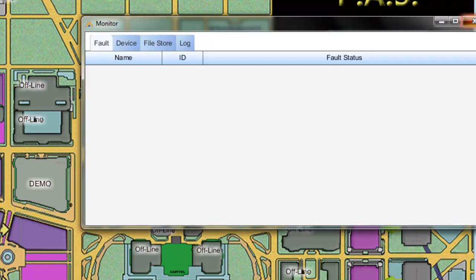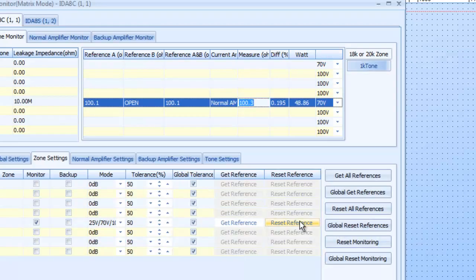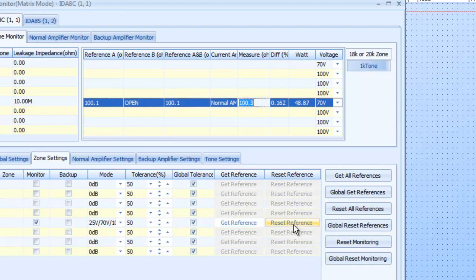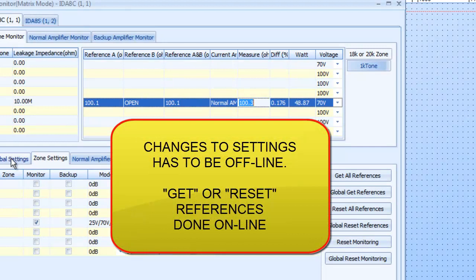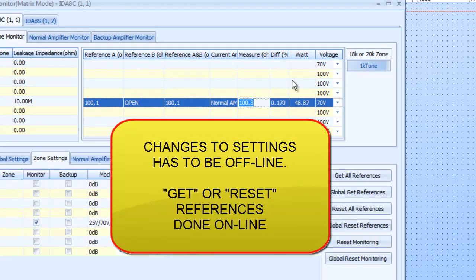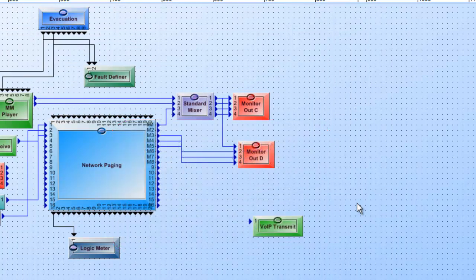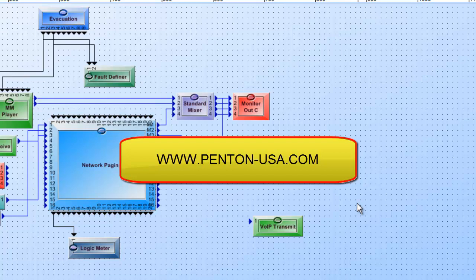All right. So that is a very quick demo. And like I said it was very easy on how to set up your monitoring in your system. If you had a short on your line instead of open it would say short. And then you would have to go in after you fixed it. You would have to do your global reset. If it was still shorted it would go right back into trouble. Open it up. But once you fixed it then reset all references. Or you can say reset that one reference and then go get it again. And set your baseline and you're off and running. You can do this at any time. You can look at these measurements. You can get references and reset only when you're online. But if you're changing any of your settings or tolerances that can only be done when you're offline. This helps you get started with your IDA 8 and setting up your line supervision. Thank you once again. And please have a terrific day.